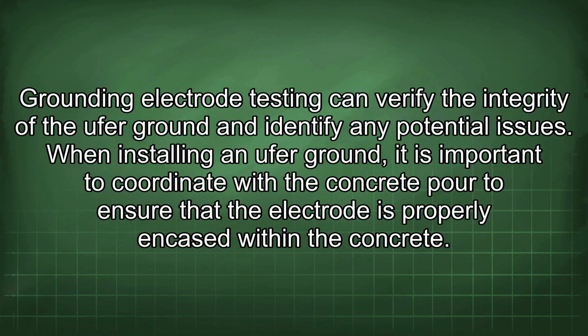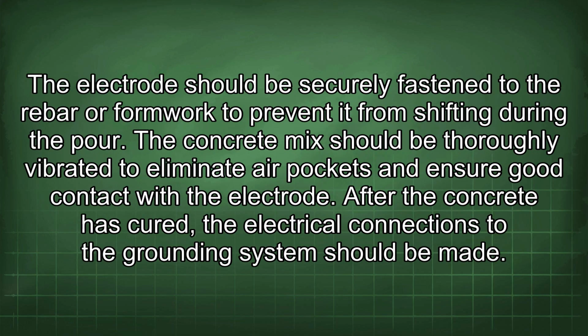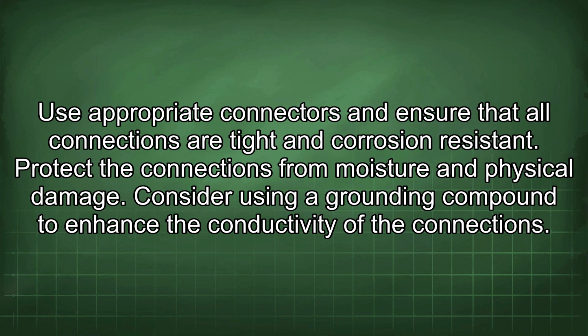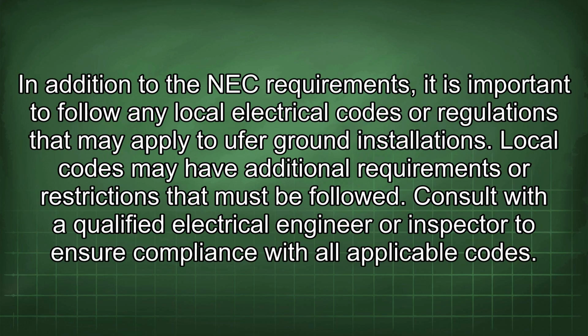When installing a Ufer ground, it is important to coordinate with the concrete pour to ensure that the electrode is properly encased within the concrete. The electrode should be securely fastened to the rebar or formwork to prevent it from shifting during the pour. The concrete mix should be thoroughly vibrated to eliminate air pockets and ensure good contact with the electrode. After the concrete has cured, the electrical connections to the grounding system should be made. Use appropriate connectors and ensure that all connections are tight and corrosion resistant. Protect the connections from moisture and physical damage. Consider using a grounding compound to enhance the conductivity of the connections. In addition to the NEC requirements, it is important to follow any local electrical codes or regulations that may apply to Ufer ground installations.